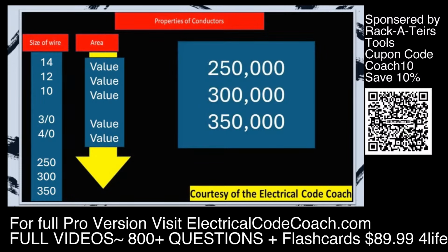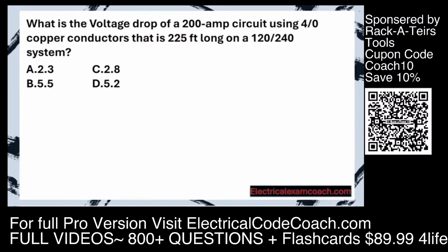So once you get past 4/0, you're going to get into 250, 300, 350, and all you have to do is add on the 3 zeros. What is the voltage drop of a 200 amp circuit using 4/0 copper conductors that is 225 foot long on a 120/240 volt system?